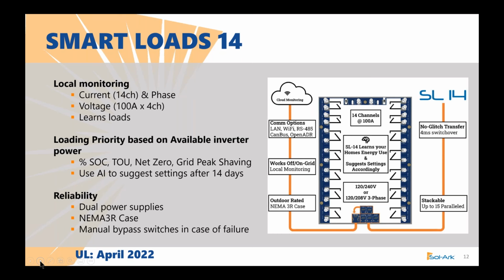Can your software derate the 15 kilowatt unit to 10 kilowatt AC max output? There are micro DG rules in Ontario, Canada that limit small projects to 10 kilowatt AC, so we can reduce the sell back to the utility, which is what they're typically worried about. We can control that sell back to a value anywhere from 1 watt to 15 kilowatts. It will be adjustable, but you will not be able to control the load output amount of the inverter—sell back can be controlled, but not load output.